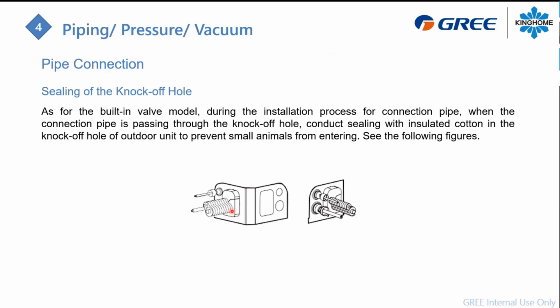The refrigerant line passes through a hole in the corner panel. So just make sure the hole is blocked. The knockout hole will be blocked after you have done all your work, around your low voltage wire, high voltage wire, and then your 3/8 pipe and 3/4 pipe. The unit is installed outside, so maybe some small animal can enter because it's warm inside that cabinet. If you don't want a small mouse eating all the electronic stuff inside the unit, make sure the hole is sealed properly. So this is an important thing to know too.